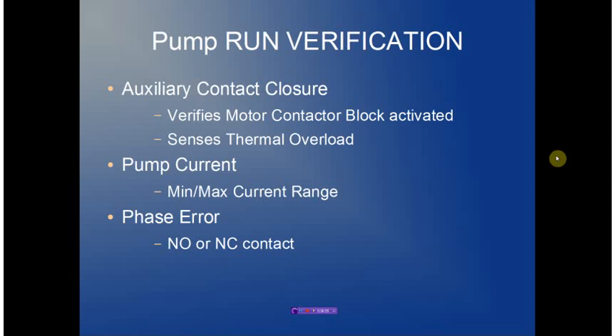Pump run verification looks at the auxiliary contact closure, which first ensures the motor contact block has been activated. If it opens while the pump is running, it indicates a thermal overload condition. Pump current is monitored, and both minimum and maximum levels can be set as trip points. Finally, the phase error contact allows an external phased monitoring relay to be applied — again, either a normally open or normally closed contact.